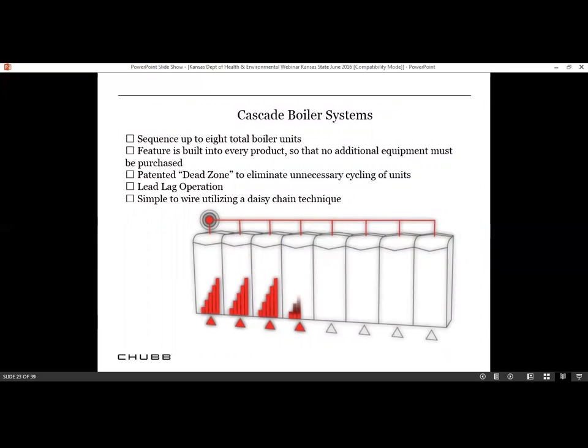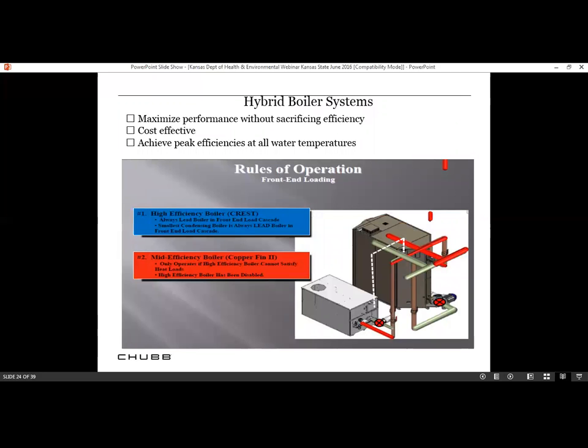Cascade boiler systems, the sequence of these systems are up to 8 boilers. They come on, and if you look down there at the drawing, they are used when they need to be. They're a daisy chain type setup, and that's what you would see in a school that had some large steam boilers. Now they put in about 8 of these units. There's hybrid systems where you have one large high efficiency boiler, and it's the lead boiler all the time. And if you get into a situation where the temperature is real low, then the second boiler will come on and sort of compensate for it.